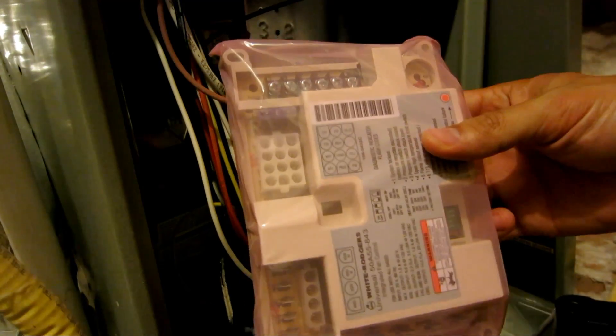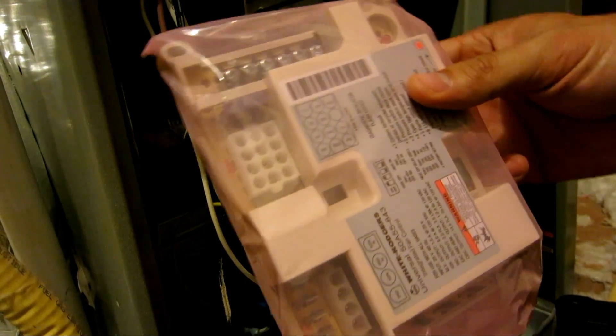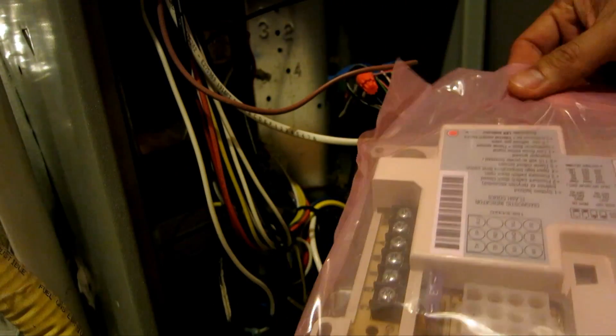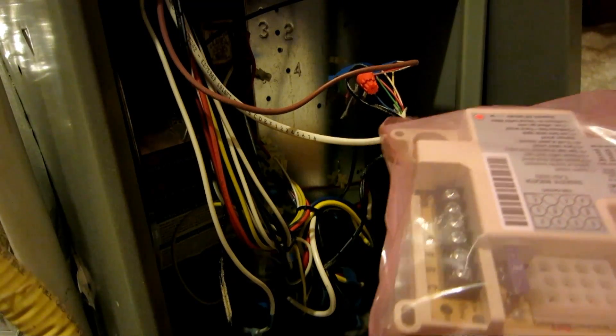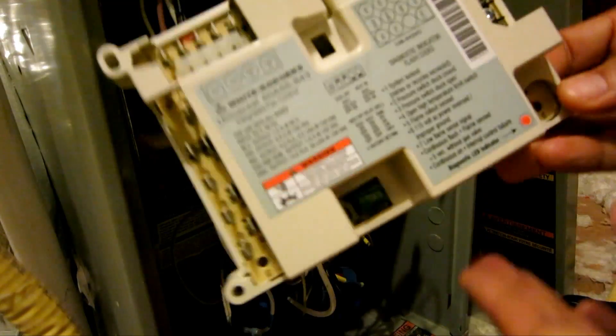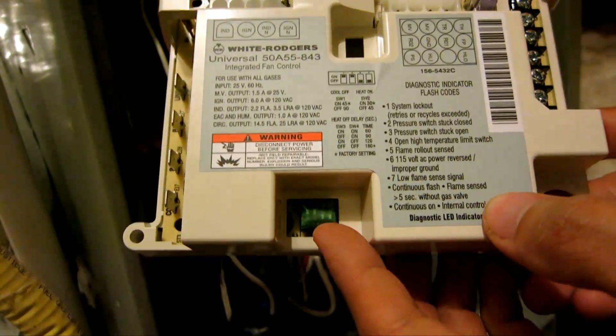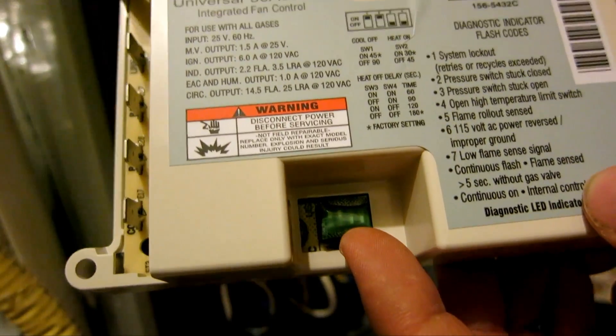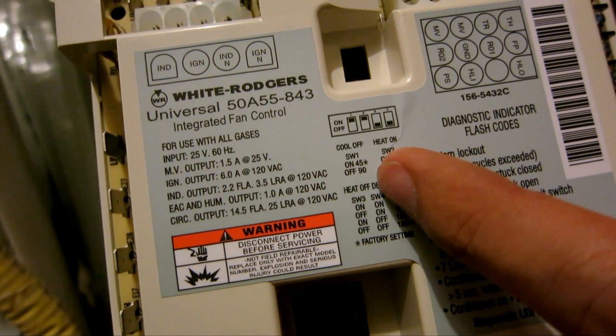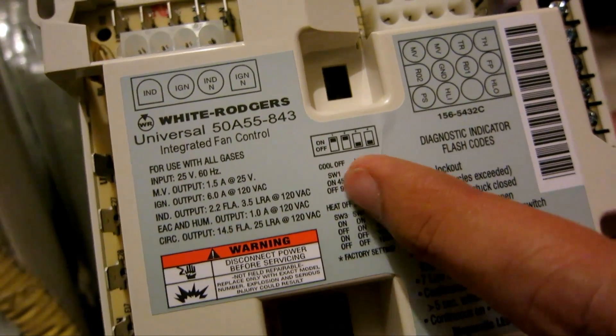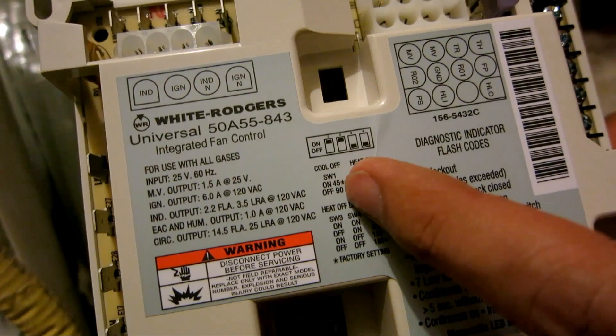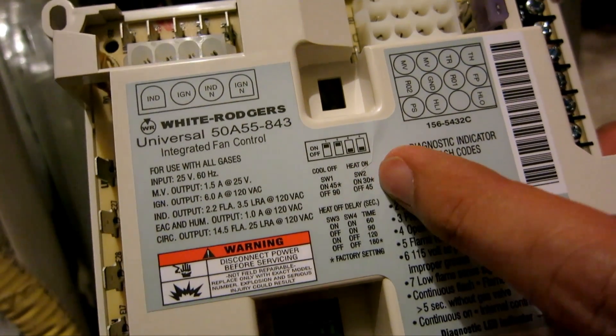So here's a new board, and the only difference on the new board, because it replaces a couple of different models, is there's this DIP switch down here. The DIP switch corresponds to how much delay you want the cool to come on, how much delay you want the heat to come on, and how much delay you want the heat to turn off afterwards.